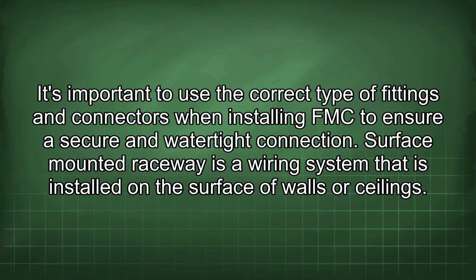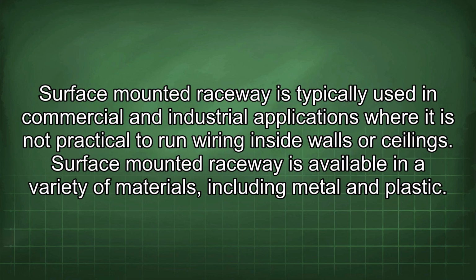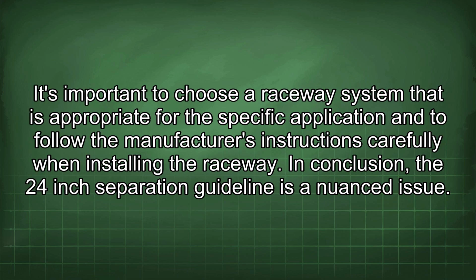connection. Surface-mounted raceway is a wiring system that is installed on the surface of walls or ceilings. Surface-mounted raceway is typically used in commercial and industrial applications where it is not practical to run wiring inside walls or ceilings. Surface-mounted raceway is available in a variety of materials, including metal and plastic. It's important to choose a raceway system that is appropriate for the specific application and to follow the manufacturer's instructions carefully when installing the raceway.